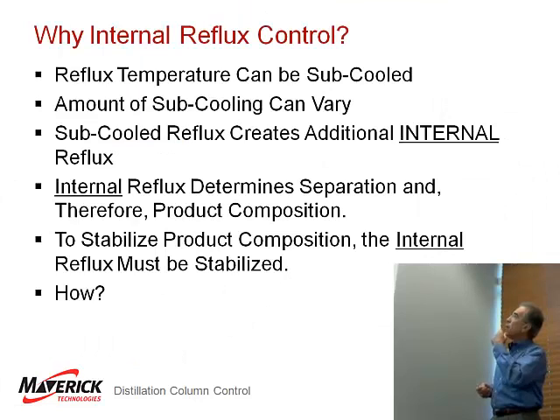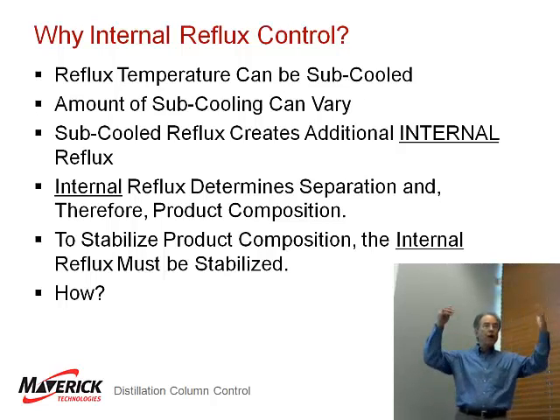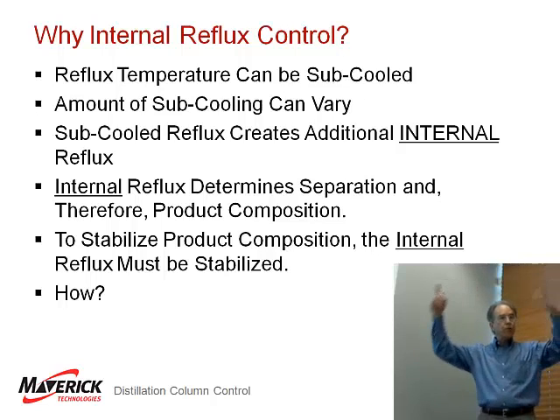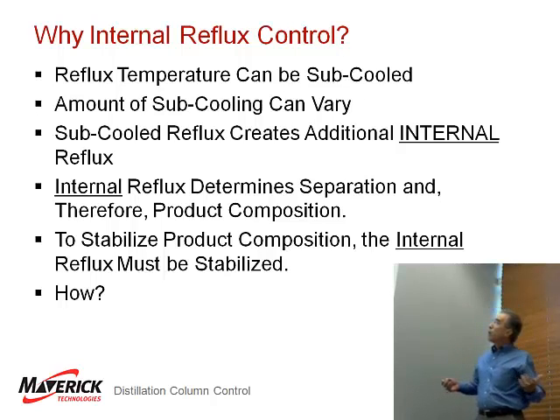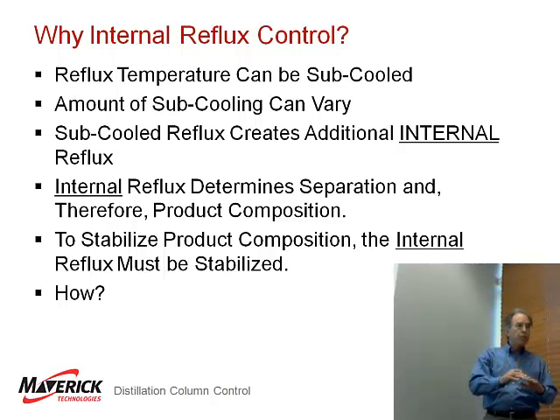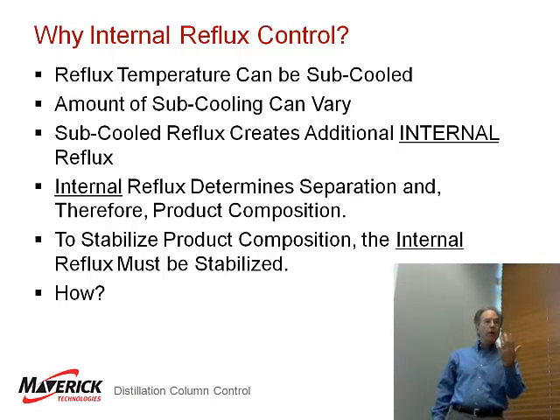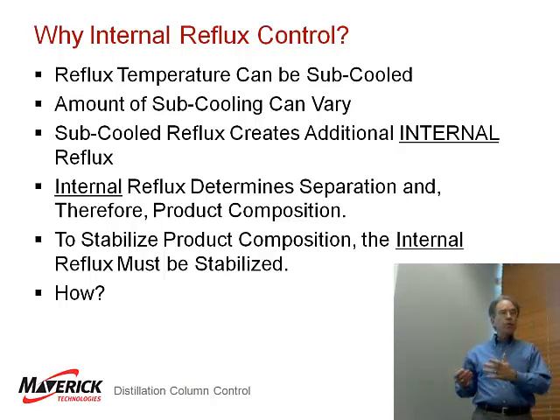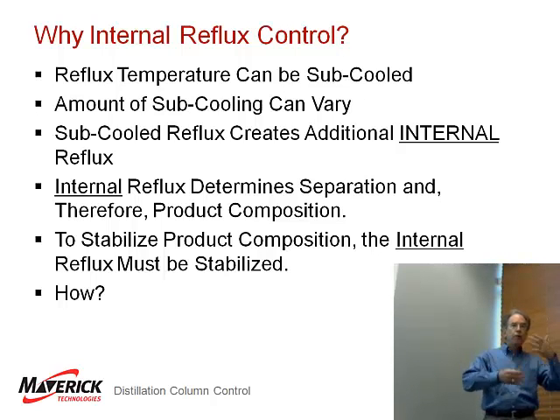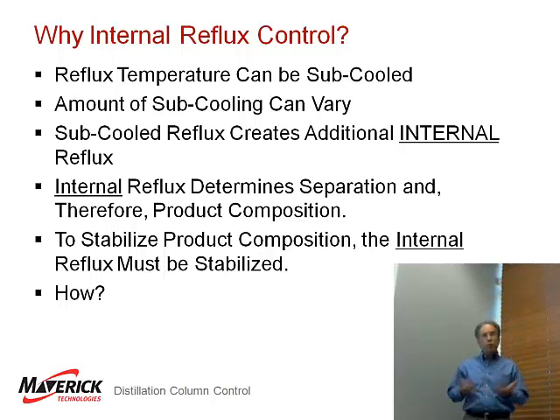Why internal reflux control? Reflux can be subcooled, and the amount of subcooling can vary. For example, if you have an air fan condenser and a rainstorm hits, your reflux temperature suddenly gets much cooler. Subcooled reflux has additional internal reflux because when it enters the tower, it's below its bubble point, so it takes heat to vaporize it. That heat comes from condensing vapor rising from the trays below, creating more internal reflux. The more subcooled the reflux, the more actual internal reflux you have — which is a disturbance that changes the vapor-to-liquid ratio and upsets composition.